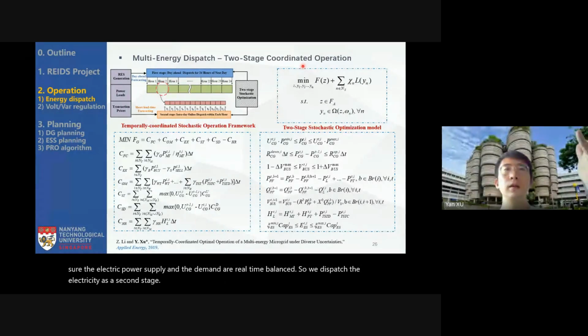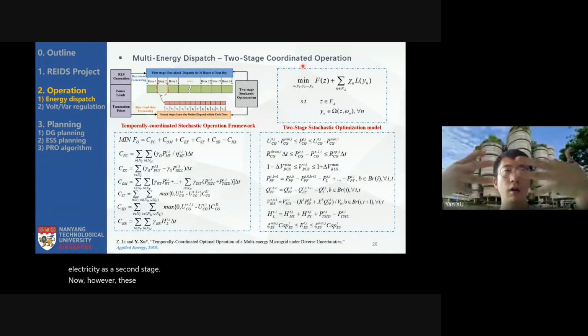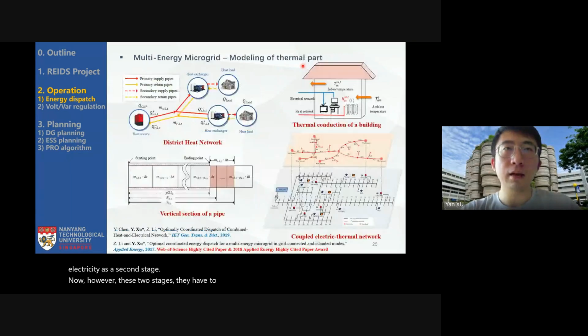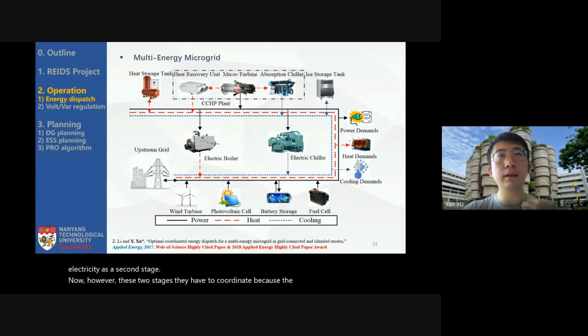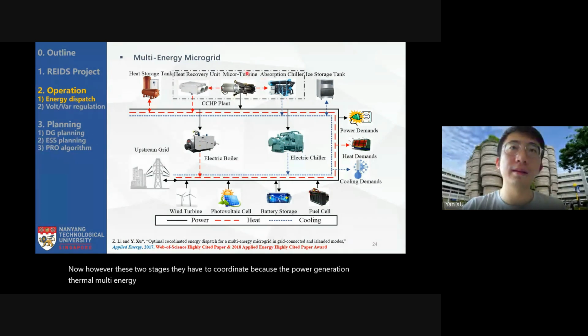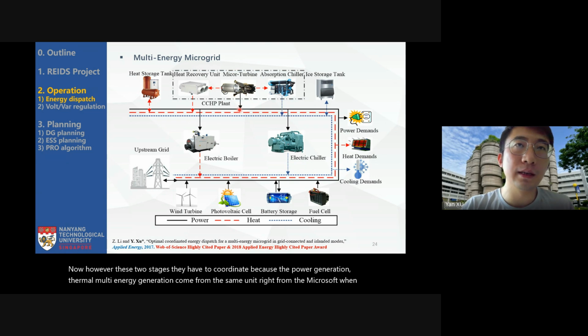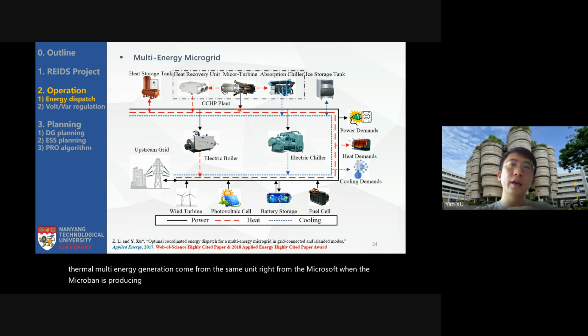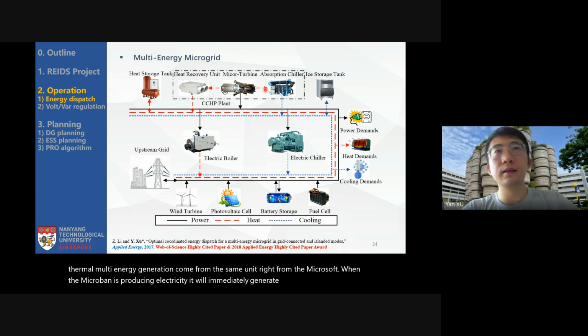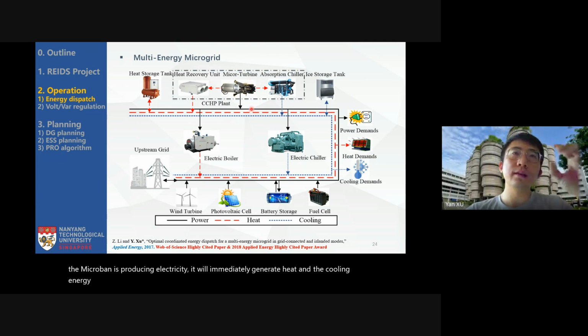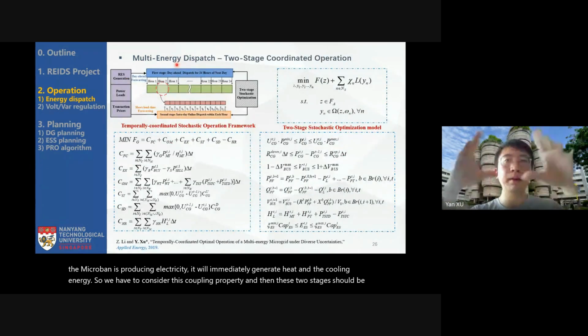However, these two stages have to coordinate because the power and thermal multi-energy generation come from the same unit, the microturbine. When the microturbine is producing electricity, it will immediately generate heat and cooling energy. So we have to consider this coupling property, and these two stages should be coordinated in a mathematical way.